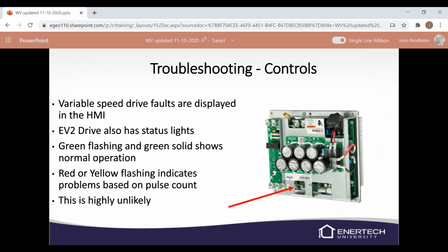The variable speed drive faults are displayed on the HMI, but it does have status lights. So a green flashing and a green solid show normal operation. Anytime you see a red or yellow flash, it'll normally indicate a problem, and it's based on the pulse count. I don't know what those pulse counts mean. You'll have to let me know what they are, and I'll check with our engineering department on that. Highly unlikely that we have that issue.